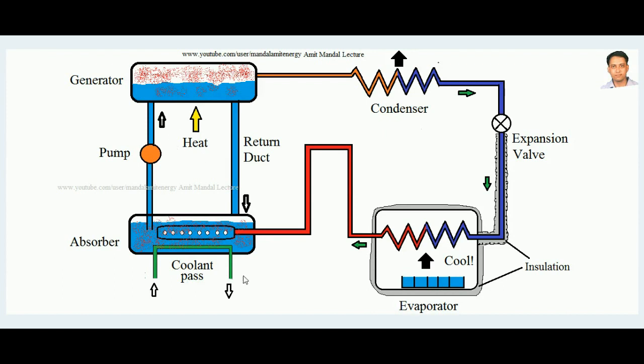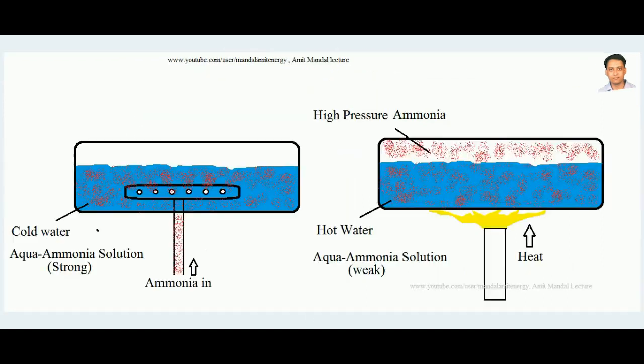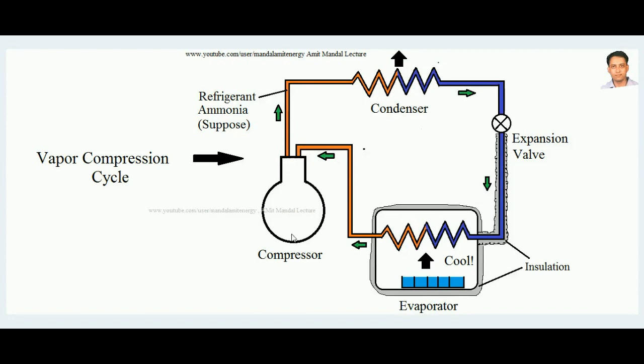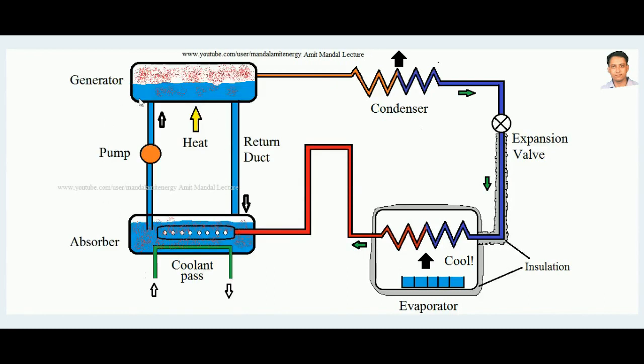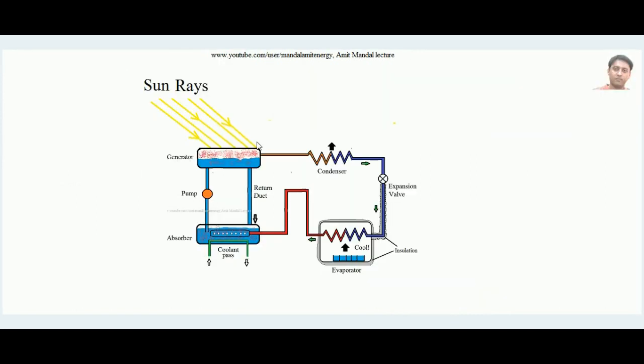Although the compressor is removed, a pump is still required. You might think the pump needs the same electrical energy as a compressor, but the amount of electrical energy required by the pump is very much less compared to the compressor. With very little electrical power input, a higher amount of refrigeration effect can be developed — much less than the power required when using a compressor in the vapor compression cycle.